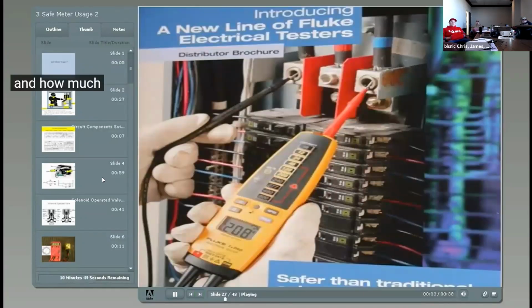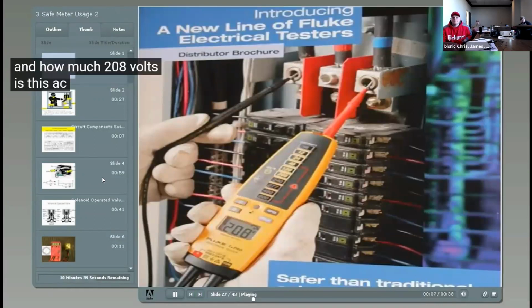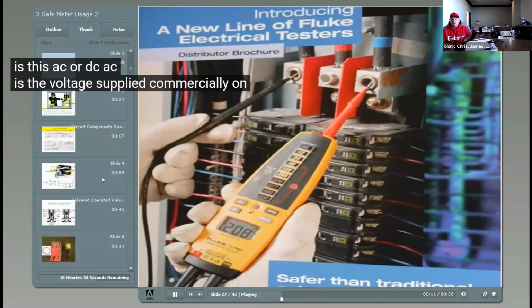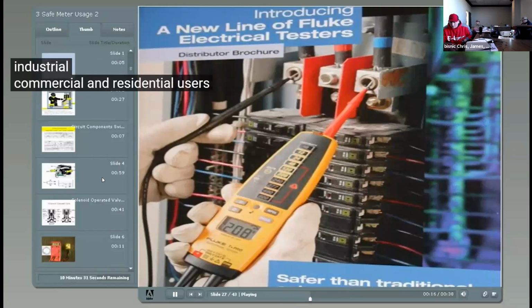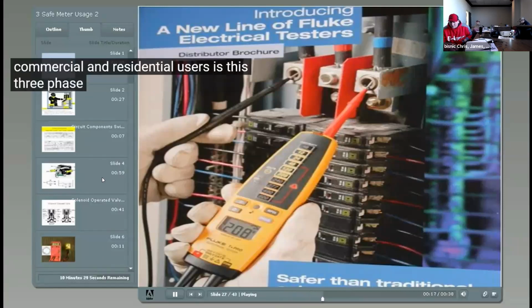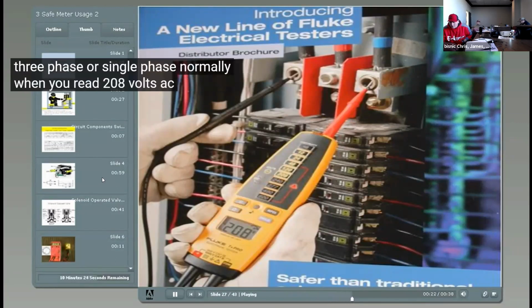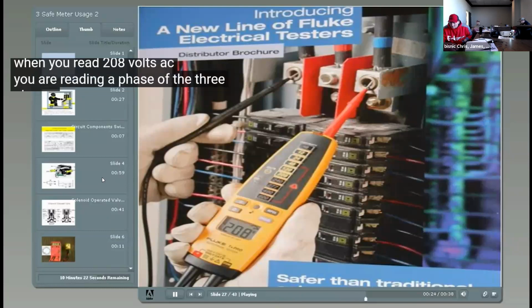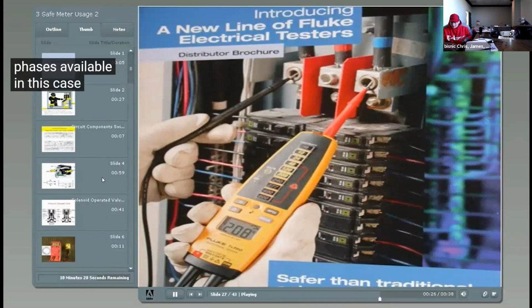And how much? 208 volts. Is this AC or DC? AC is the voltage supplied commercially on the electrical grid around the world to industrial, commercial, and residential users. Is this three-phase or single-phase? Normally, when you read 208 volts AC, you are reading a phase of the three phases available. In this case, three phases are available.